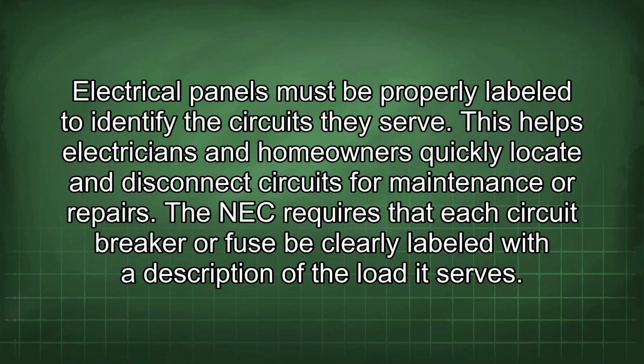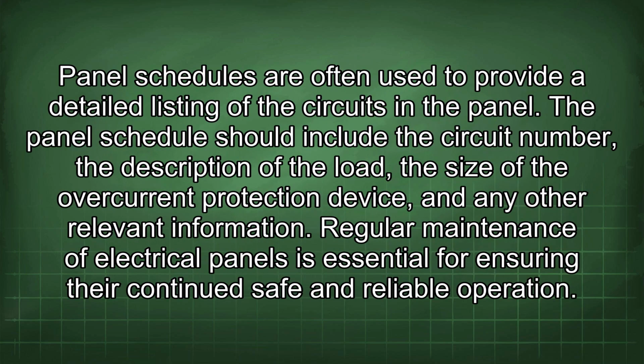The NEC requires that each circuit breaker or fuse be clearly labeled with a description of the load it serves. Panel schedules are often used to provide a detailed listing of the circuits in the panel. The panel schedule should include the circuit number, the description of the load, the size of the overcurrent protection device, and any other relevant information.